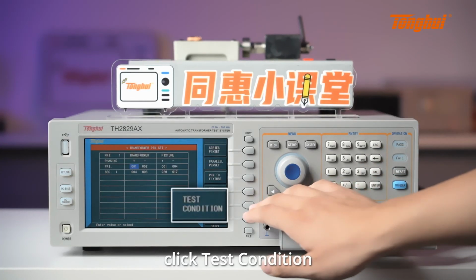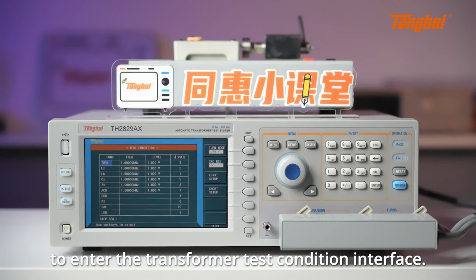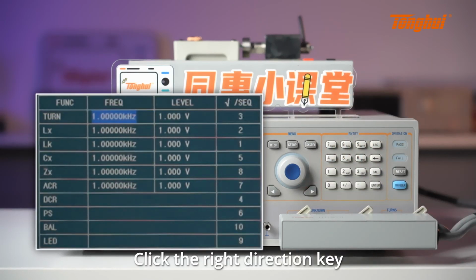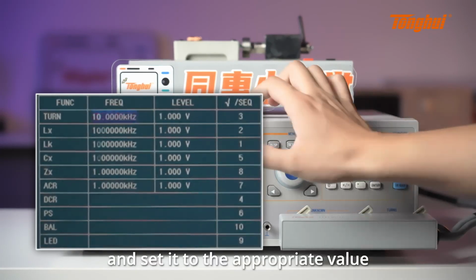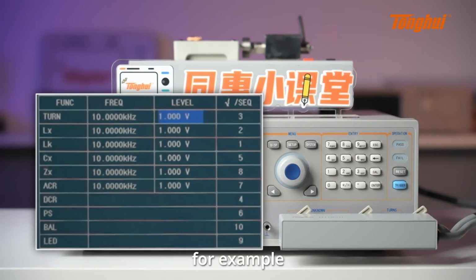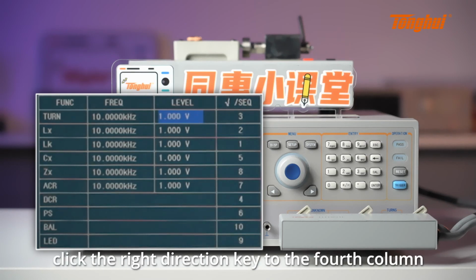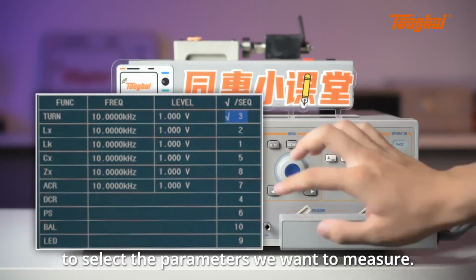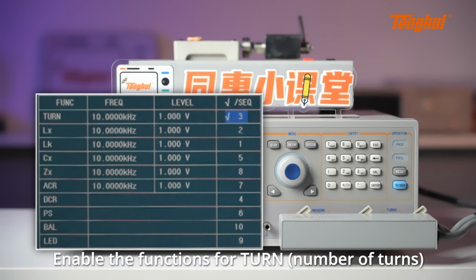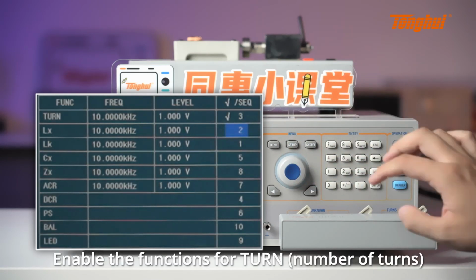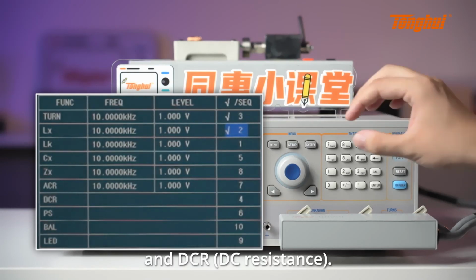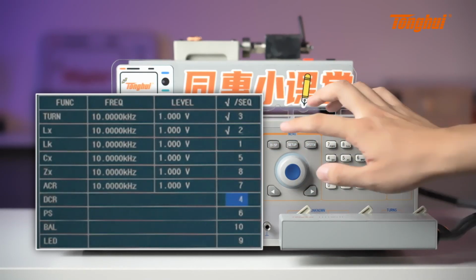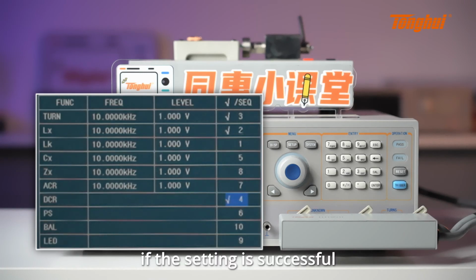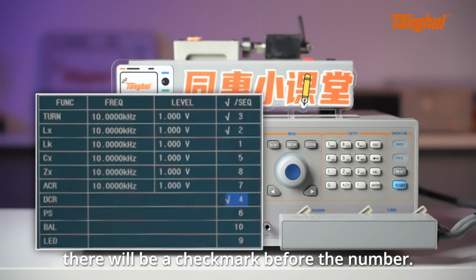Next, click Test Condition to enter the transformer test condition interface. Click the right direction key to select the frequency and set it to the appropriate value. For example, here we set it to 10 kHz and the level is set to 1 volt. After setting the frequency and level, click the right direction key to the 4th column to select the parameters we want to measure. Enable the function for turn, number of turns, LX, inductance, and DCR, DC resistance. Click On. If the setting is successful, there will be a check mark before the number.